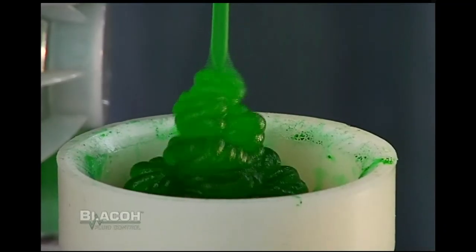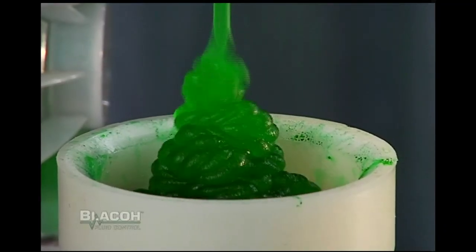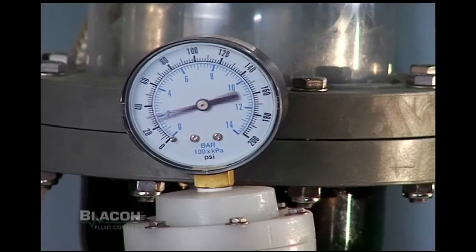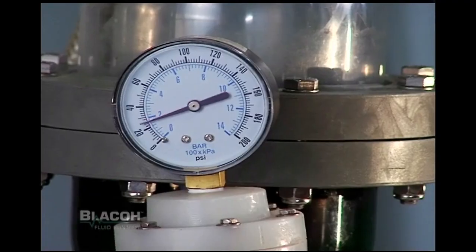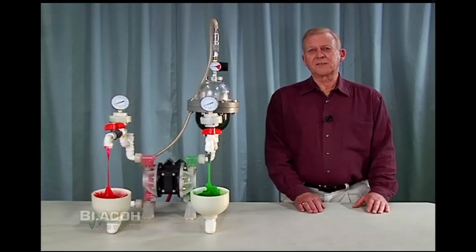The discharge manifold with the benefit of the pulsation dampener has a smooth, steady flow which can also be observed on the gauge as low pressure variations. No special consideration needs to be given for fluids under 25,000 SSU.